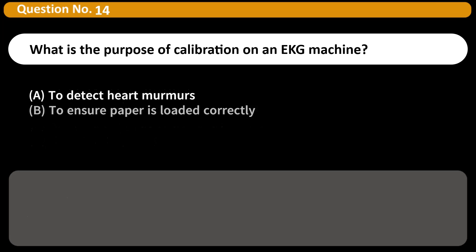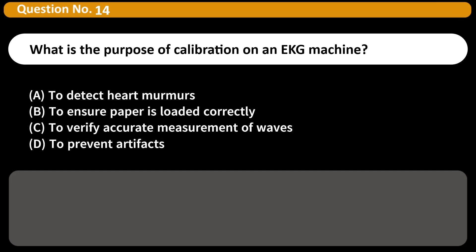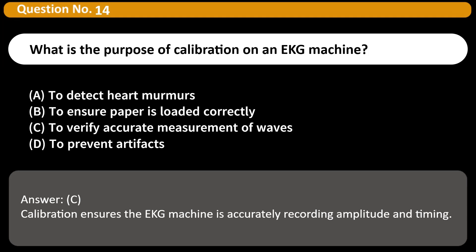What is the purpose of calibration on an EKG machine? A. To detect heart murmurs B. To ensure paper is loaded correctly C. To verify accurate measurement of waves D. To prevent artifacts Answer C. Calibration ensures the EKG machine is accurately recording amplitude and timing.